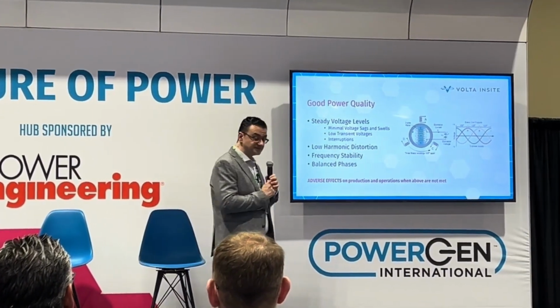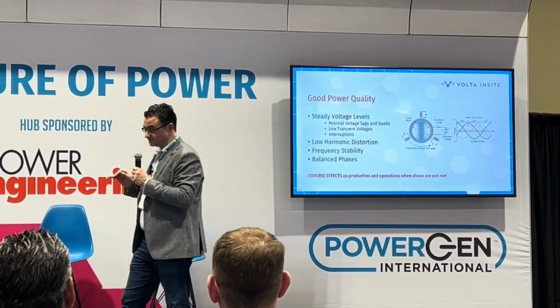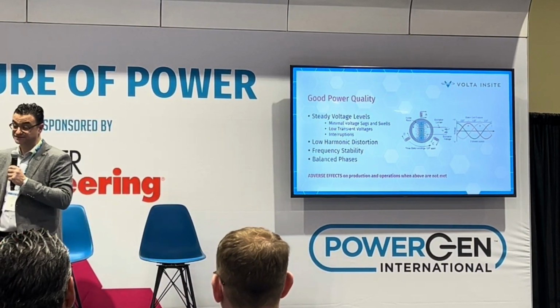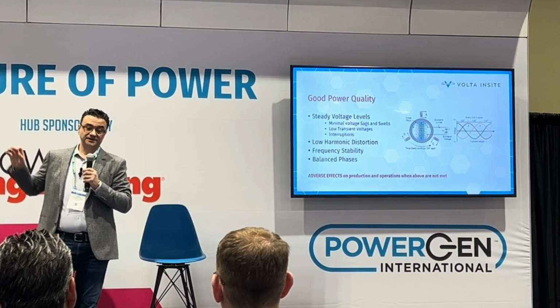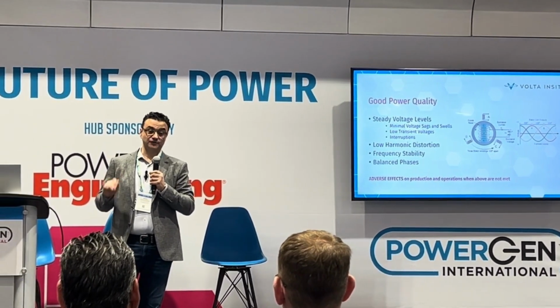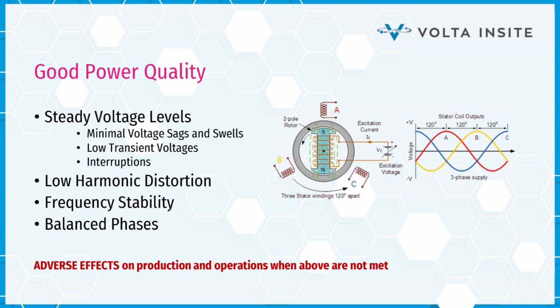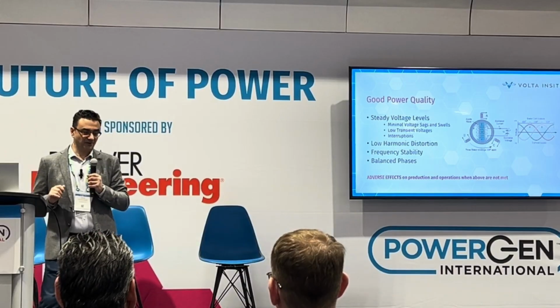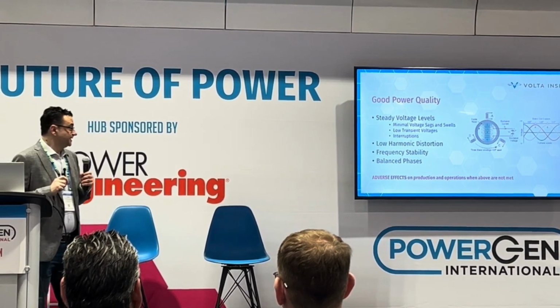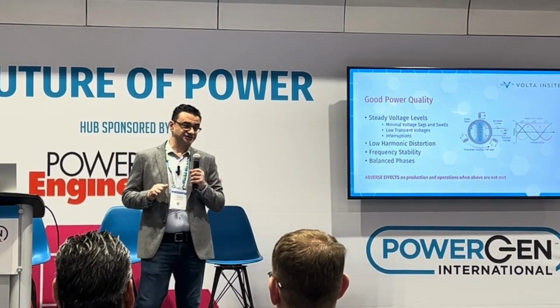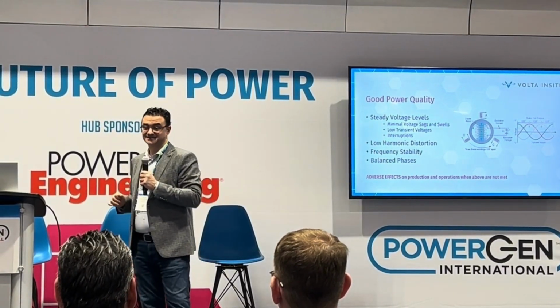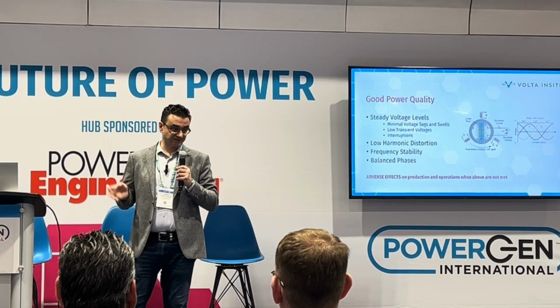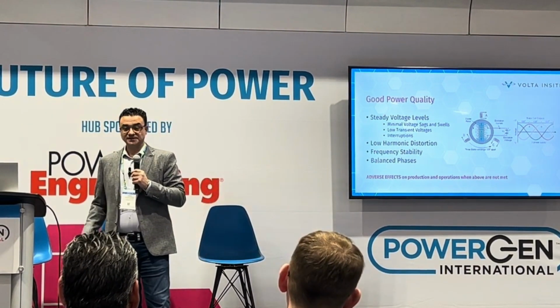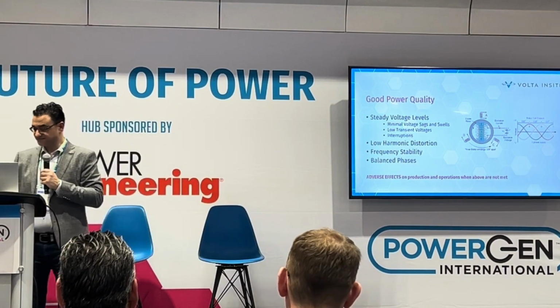quality. We want to ensure that we have steady voltage levels, whether you're producing at 20 kilovolts on your generation side or you're running a 480 volt system. We want to maintain that 480 volts. We want to maintain a low level of transients within the facility. And we want to ensure that interruptions don't happen often, so you're not dropping power. Additionally, we would like to have low harmonic distortion, which usually in today's time is attributed to a lot of VFDs and switching power supplies. And we want to ensure frequency stability and balanced phases. So let's get into it.